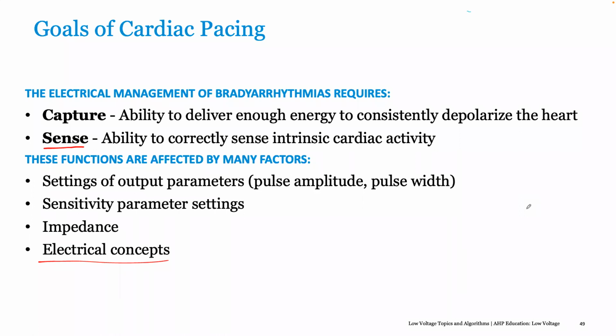Yeah, that's a good point. Abbott goes to 5 as well, just so you know, 5 volts. So yeah, I think they're great because as you said, it can give you a trend over time. But if their threshold is getting up there, if it's already at 4, then you may want to turn auto capture off and give yourself a nice 2-to-1 safety margin, and obviously schedule them for some sort of lead revision eventually, because that's going to wear the battery out quickly.